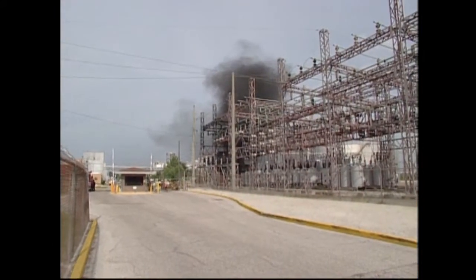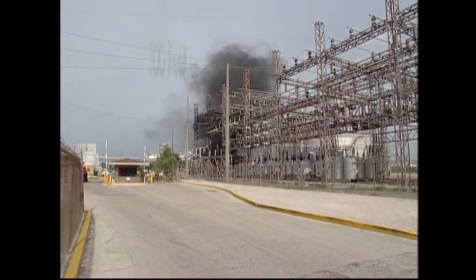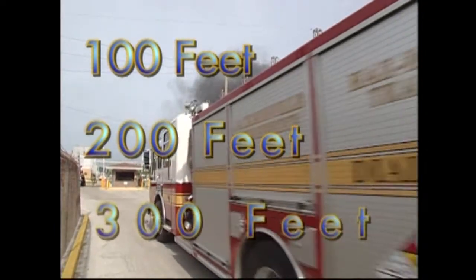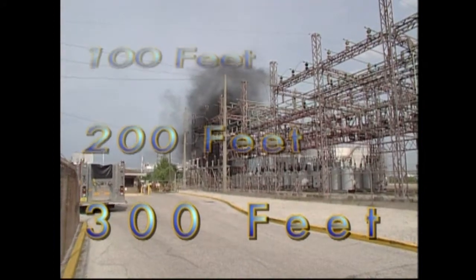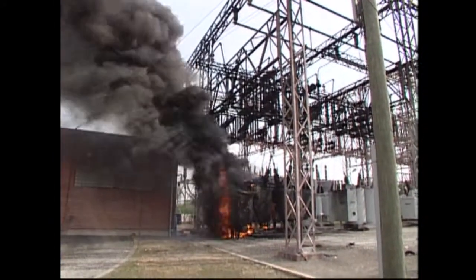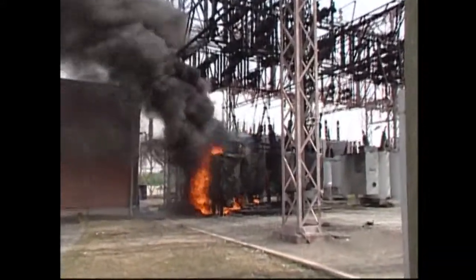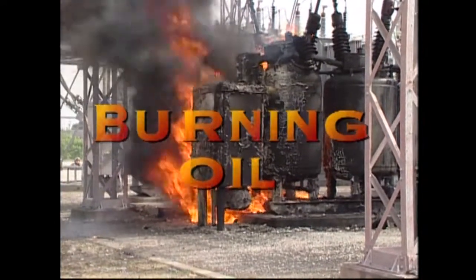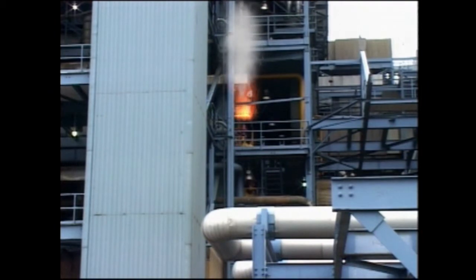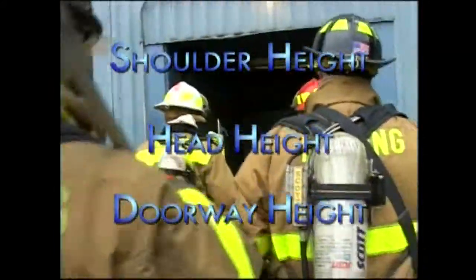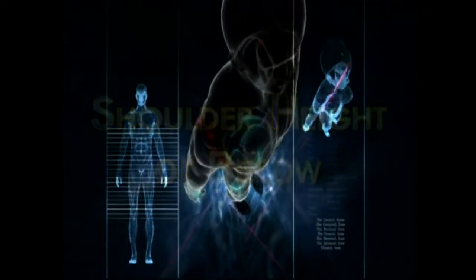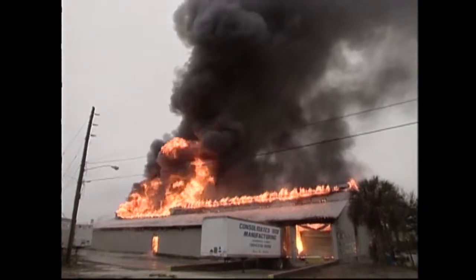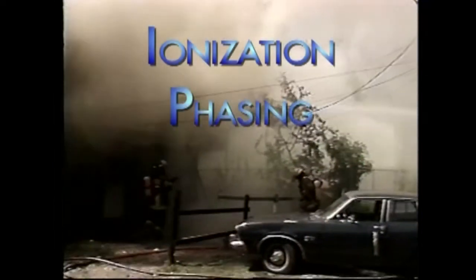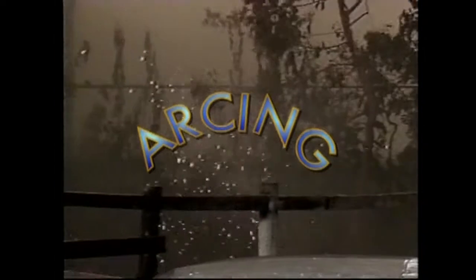If you encounter a substation fire, what is the minimum safe distance for non-essential personnel? 100 feet? 200 feet? 300 feet? 300 feet. What kind of fire are you most likely to encounter in a substation emergency? Burning oil from inside breakers and transformers. In a substation or generating plant fire, all equipment brought inside should be limited to what height? Shoulder height, head height, doorway height. Shoulder height or below. When smoke and water vapor are dense, what dangerous situation arises around transmission lines? Ionization, phasing, arcing, grounding. The current can arc through flames and smoke to you and the ground.